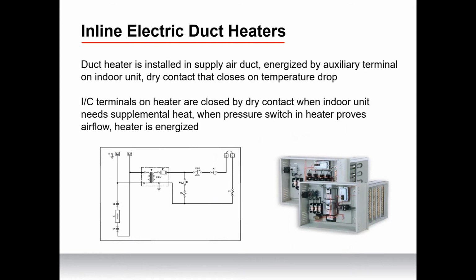You can accomplish the same thing with third-party inline electric duct heaters on the horizontal ducted indoor units. In this instance, the duct heater is installed in the supply air duct and is energized by the auxiliary terminal on the indoor unit. The dry contact closes when the desired indoor space temperature drop is reached. These heaters are built to not run unless the indoor unit fan is operating, due to fire hazard. So there's a reason we're waiting for that contact to close. When the pressure switch in the duct heater senses and proves airflow, only then will the heater be energized. So it's waiting for that. Prove airflow, then I'm going to engage my heater.